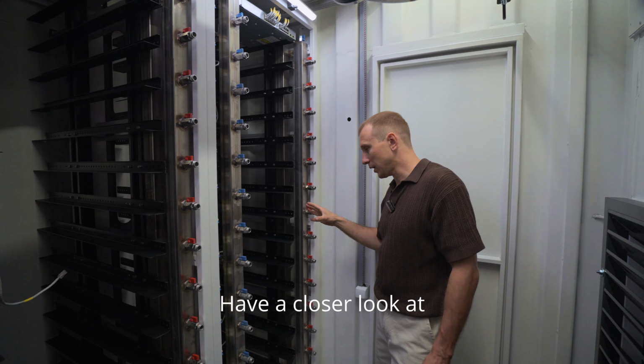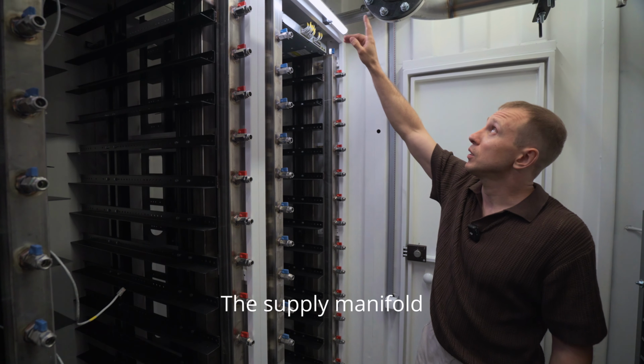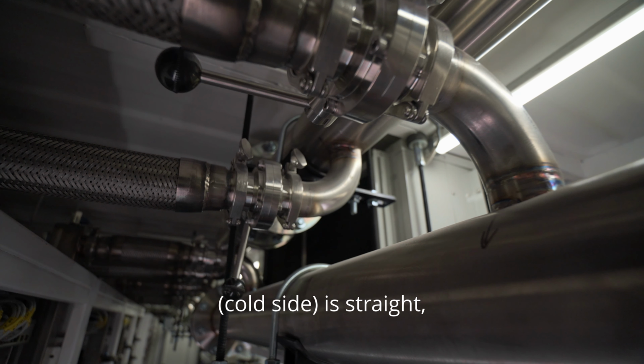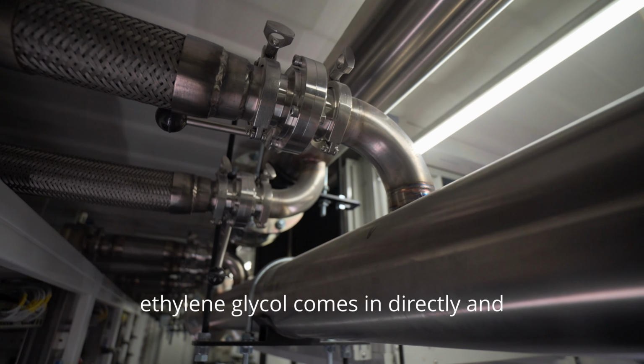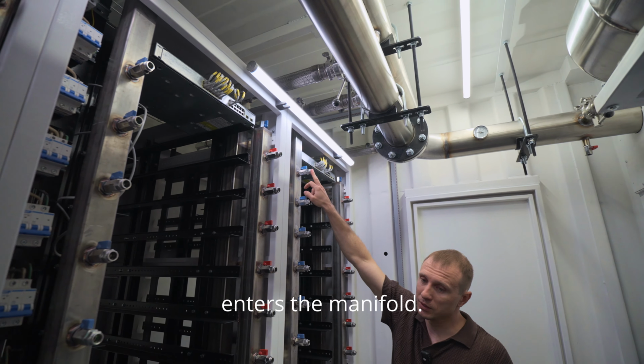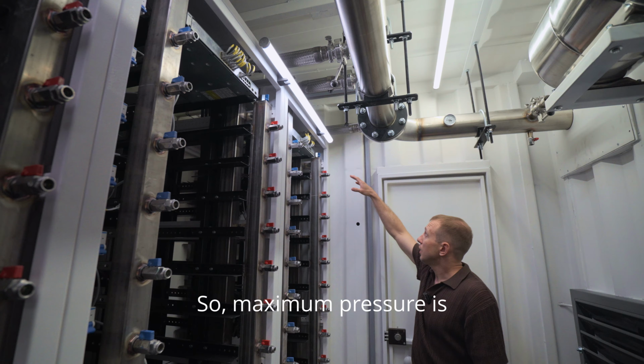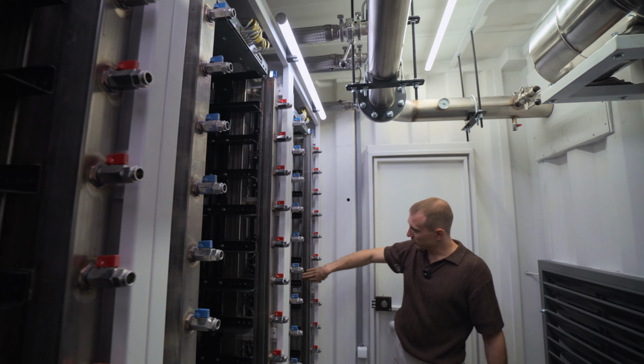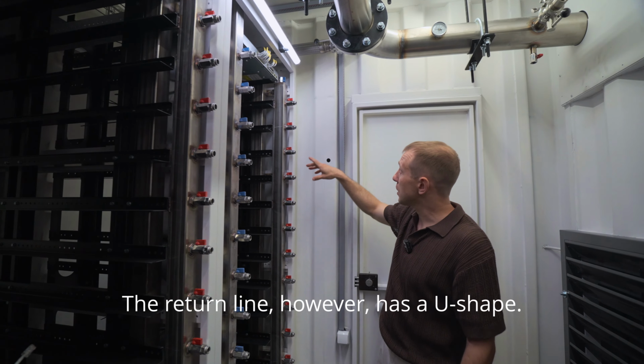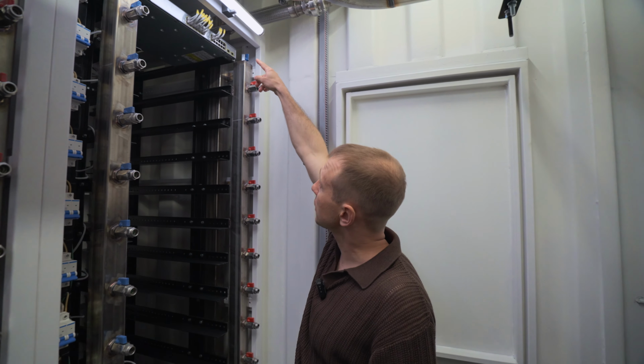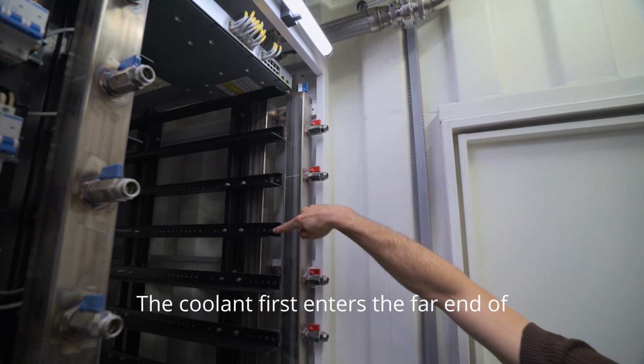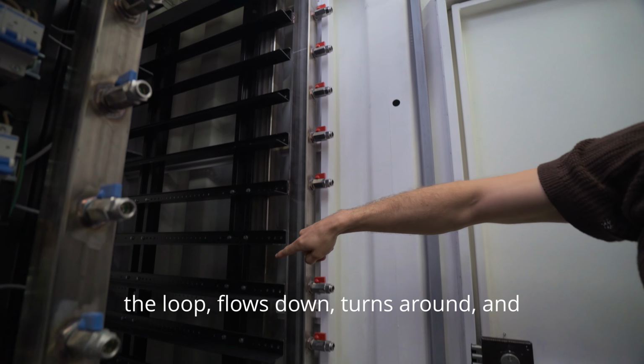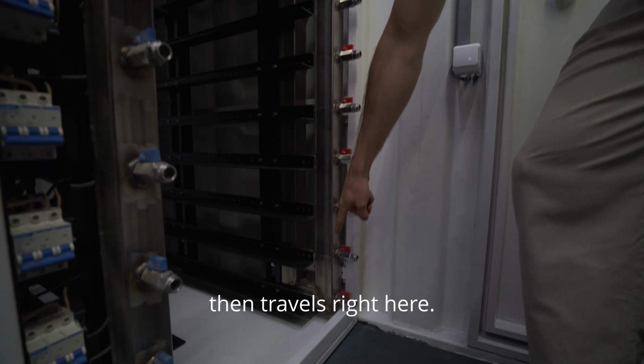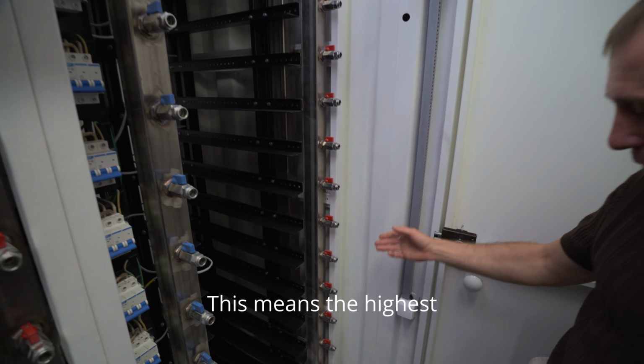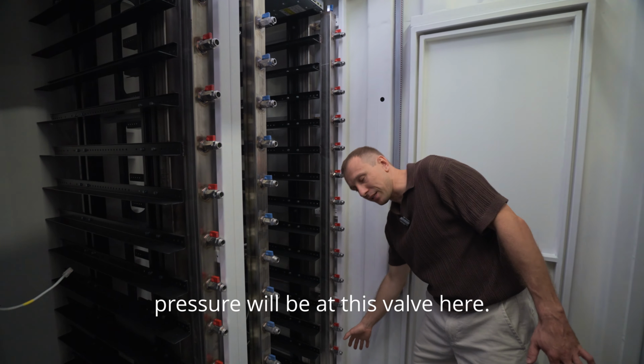Have a closer look at the manifold design. The supply manifold, cold side, is straight. Ethylene glycol comes in directly and enters the manifold, so maximum pressure is right at this first fitting. The return line, however, has a U shape. The coolant first enters the far end of the loop, flows down, turns around, and then travels right here. This means the highest pressure will be at this valve here.